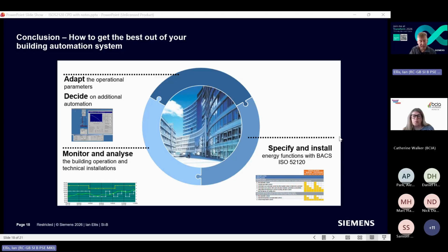Just one quick example, a bit of a schoolgirl error we still see on a lot of BMS systems, regardless of manufacturer: people set the heating and cooling set points at exactly the same value. They don't put a dead zone between the two.